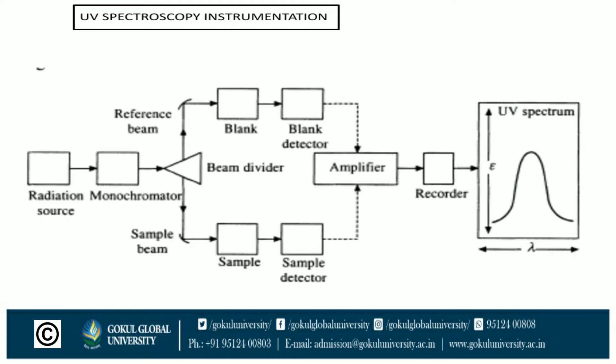The monochromatic beam is divided by the beam divider into two beams: the first is a reference beam and the second is a sample beam. The reference beam is passed through the blank or reference cell and detected by the blank detector. Similarly, the sample beam is passed through the sample cell and detected by the sample detector.